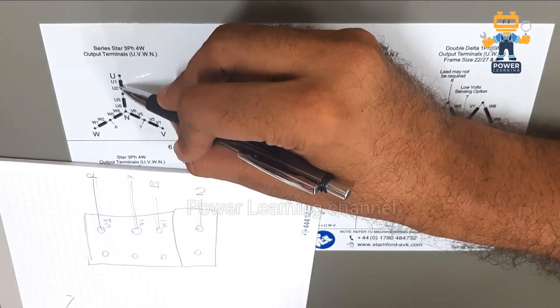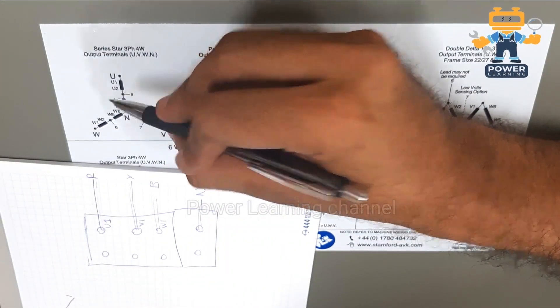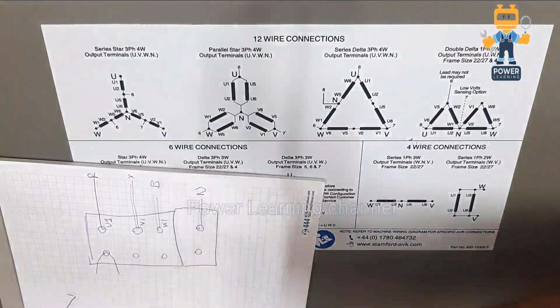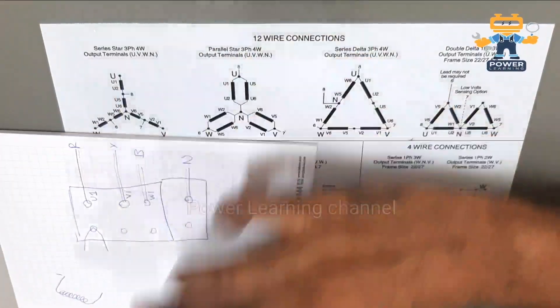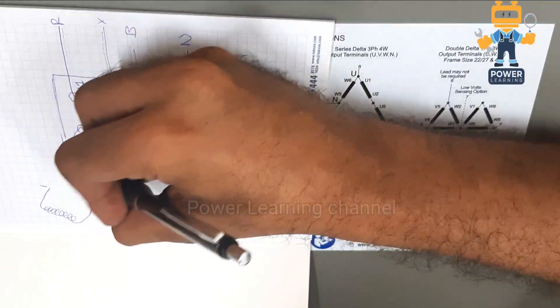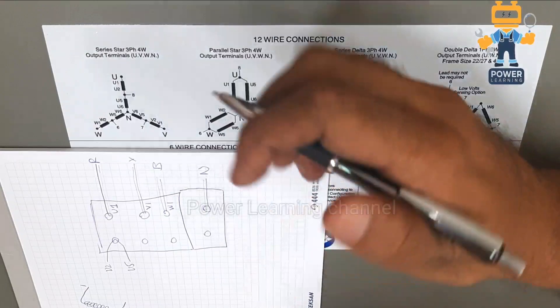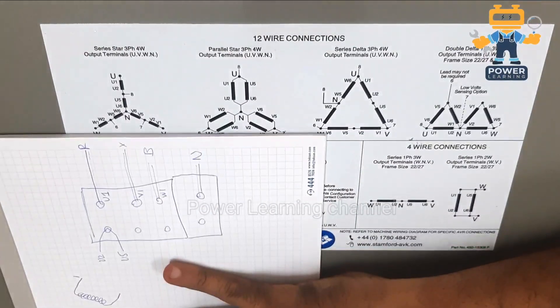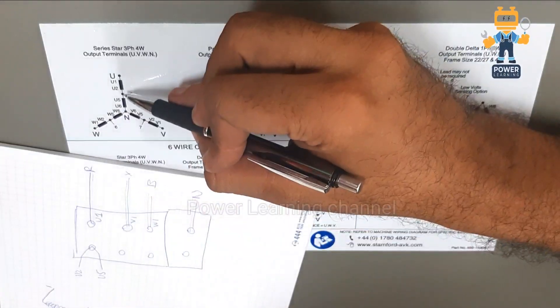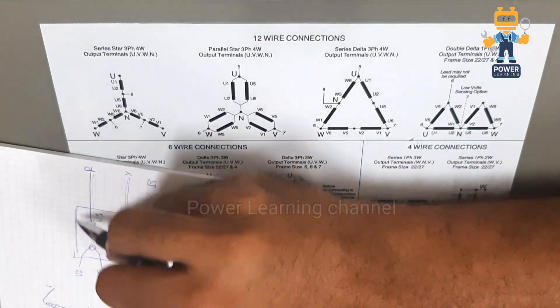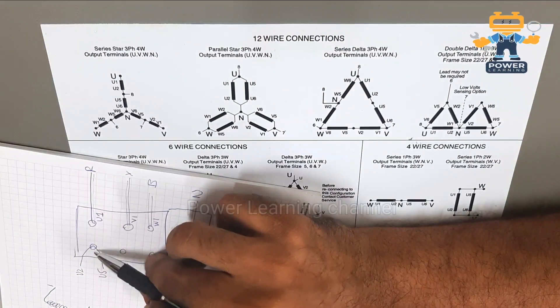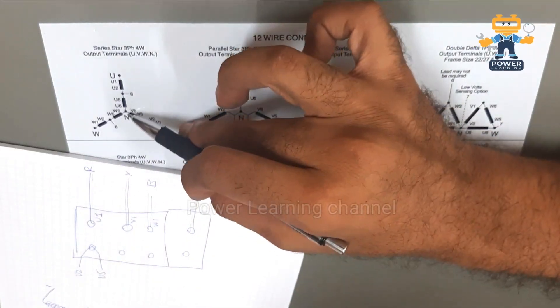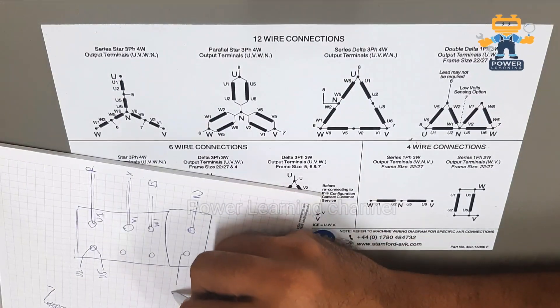After connecting the three output leads, we connect u2 with u5 — these two winding ends join together inside the terminal box. This wire comes from inside the alternator. Then from u5, the other end is u6, and u6 is connected to our neutral point.